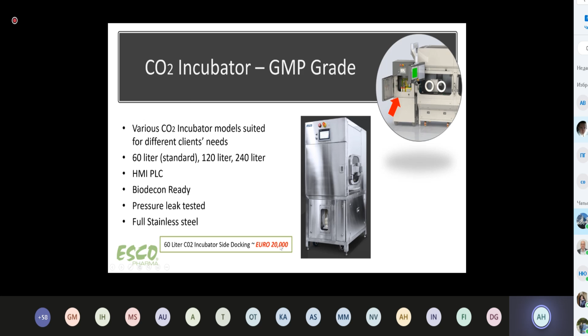Okay, a little bit more about how this incubator is connected to the isolator. You have a transition here, and this transition is surrounded by this white piece of material. We call it an inflatable seal. This inflatable seal is powered by compressed air. So when you connect the incubator to the isolator, you automatically activate a compressed air function that will balloon up the inflatable seal to give you that air tightness.